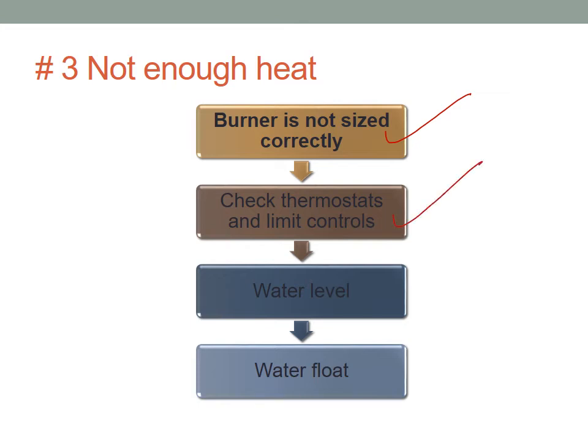Check the thermostat and limit control. Make sure you compare the temperature reading on the thermostat with an outside thermometer. Sometimes maybe it's miscalibrated, needs to be changed, or needs to be recalibrated if it's manual. Check the water level. You could be running with low water, and that will have you not circulate enough heat throughout the system. And check the water float in a water system.